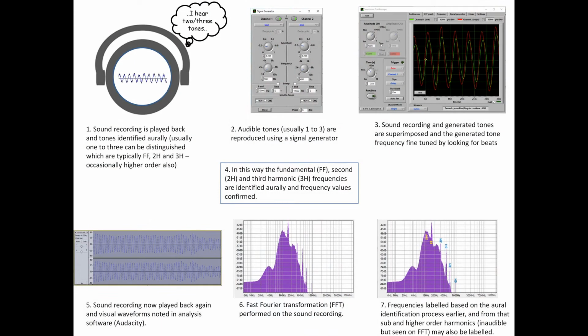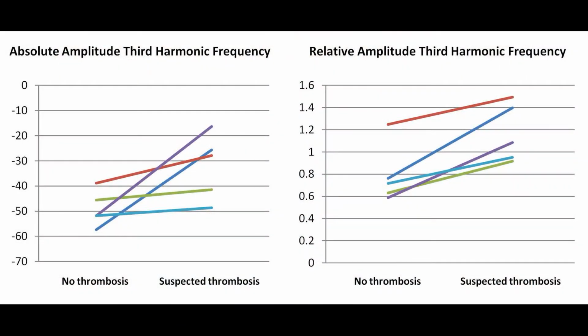It's actually on the first figure in the paper, where you can reliably pick out 3 tones. And you can see that actually in all 3 devices. But with the HeartMate 3, it probably has the most balanced representation of all the harmonics. The HeartMate 3 also has the 7th harmonic. That's very interesting. That's probably where the area of interest is, in these higher order harmonics, because specifically what we're seeing is that the relative amplitude of that 3rd harmonic, that high G, is amplified compared to the fundamental middle C in the setting of thrombosis in the HeartMate 2.